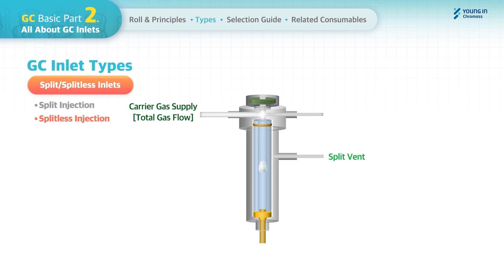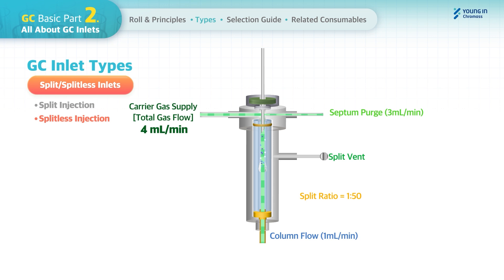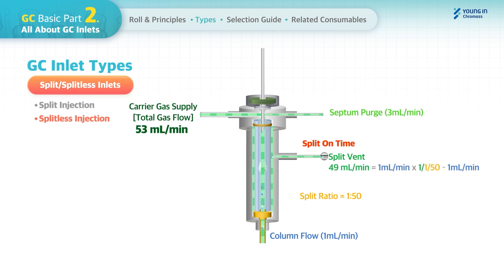With the splitless injection mode, the total gas flow goes to the septum purge and the column flow initially. For example, with a column flow of 1 mL/min and a split ratio of 1:50, the split ratio is applied at split-on time and the total gas flow is about 4 mL/min. After sample injection, the sample remains in the liner briefly before entering the column. The split vent line is closed until split-on time, after which it opens and total gas flow is adjusted accordingly.